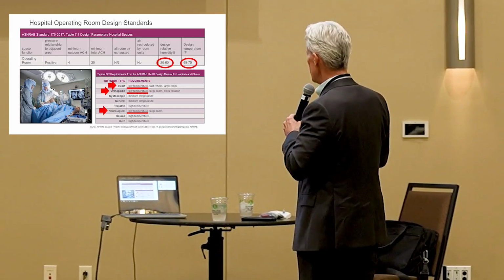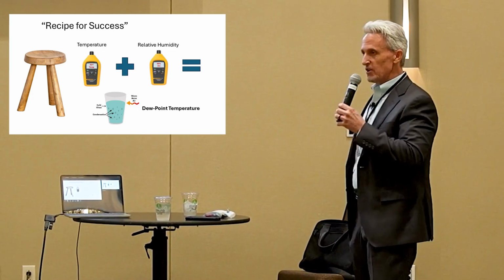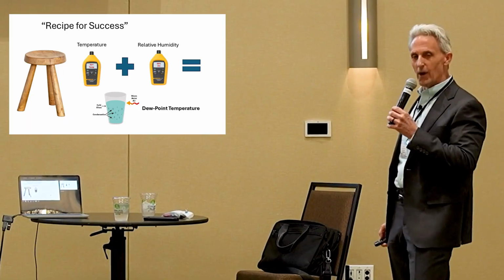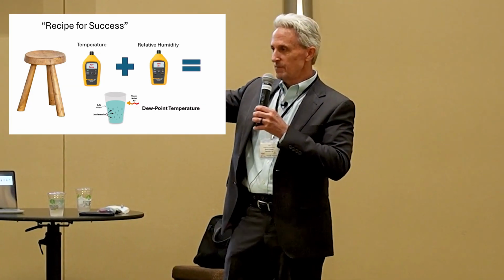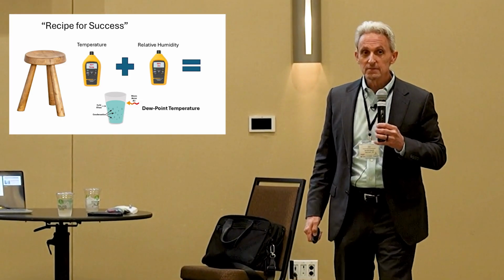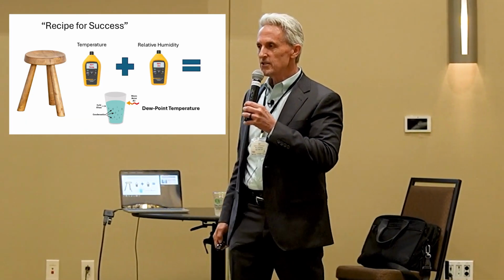Okay? Let's keep going. So, hospital operating room environmental design is a three-legged stool. Certainly temperature is important. Again, dry bulb temperature, the temperature on the thermostat, it's a part of the standard, right? 68 to 75 or whatever. I don't even remember. Doesn't matter. Doesn't work. As well, relative humidity, 20 to 60%. We know that's important. We've got two legs of the stool. The third leg is dew point temperature because it's so important to assessing how well we're dehumidifying the air. And I'm going to prove that to you in the next few slides.